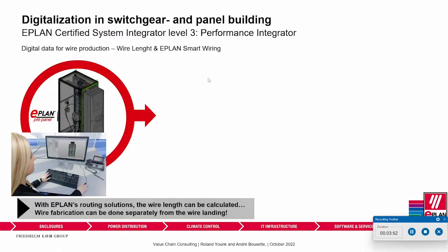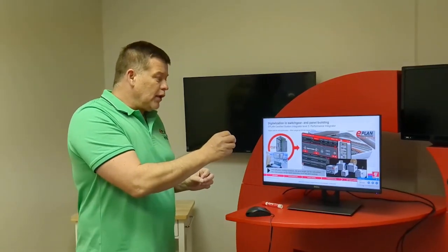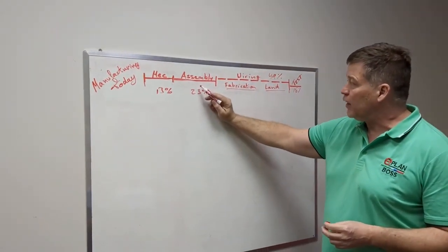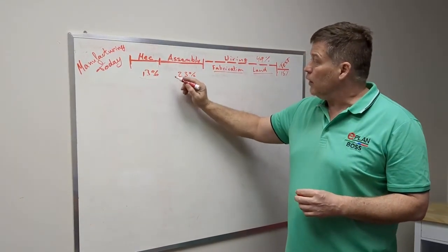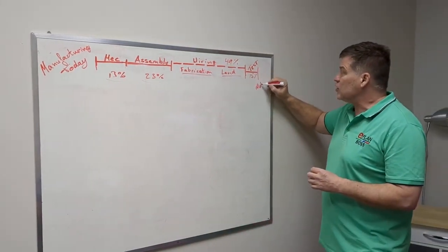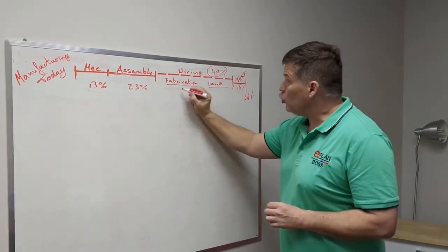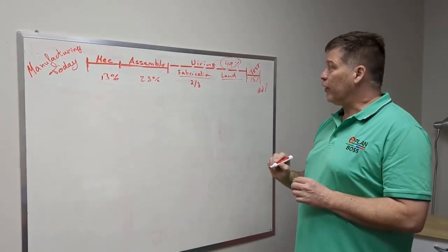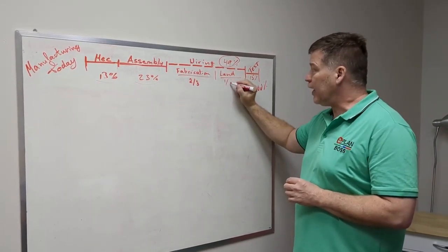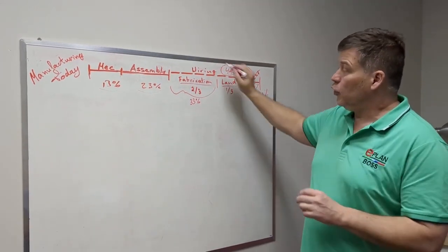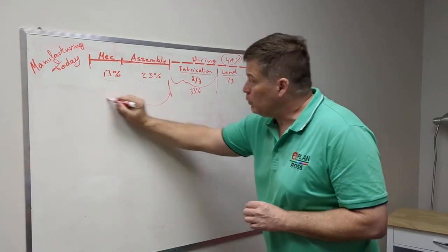The third level is the Performance Integrator. He actually uses the routing solutions of ePlan to calculate wire lengths. This is a bit more complex to explain, but what it does is help you separate the wiring from the landing. Let me show you on this graphic. According to the University of Stuttgart study, 13% and 23% of the total time is spent on mechanical fabrication, and wiring represents pretty much half of your time. Two-thirds of that is wire fabrication. If you have the length, you can separate wire fabrication from landing. That 33% of your whole wiring can actually be prefabricated.